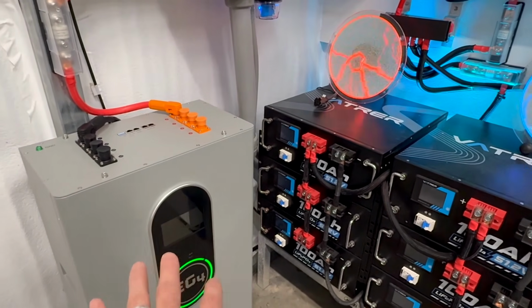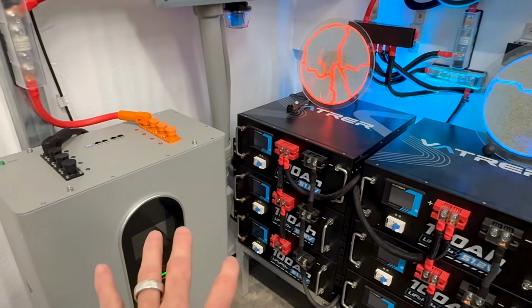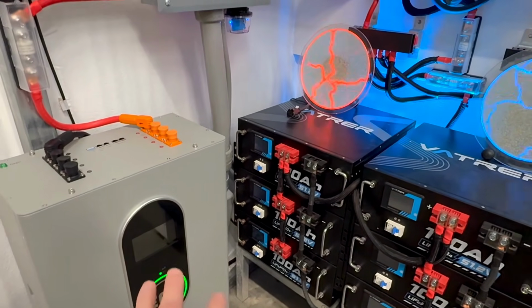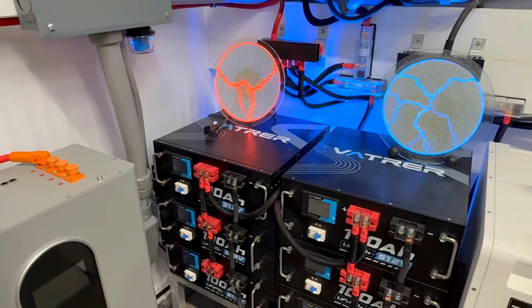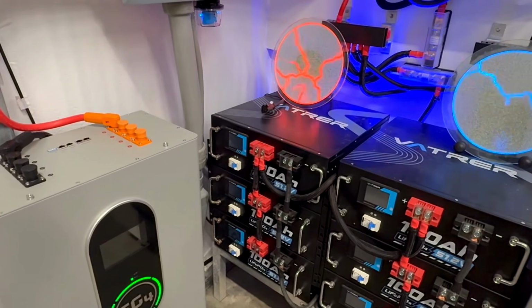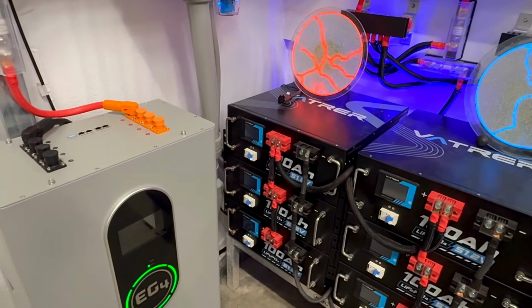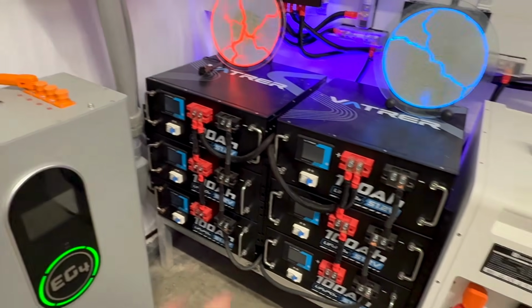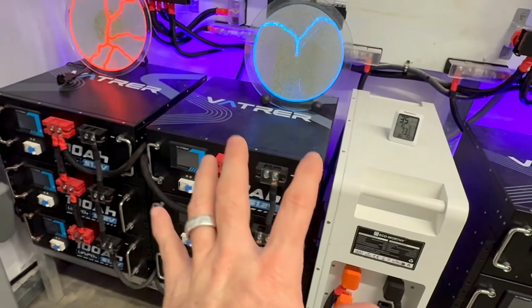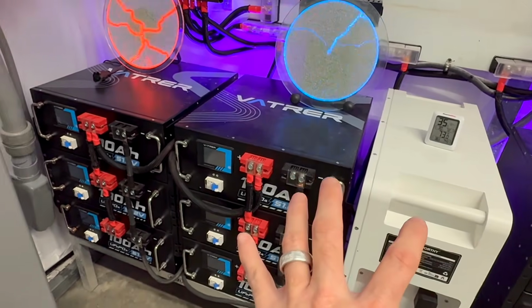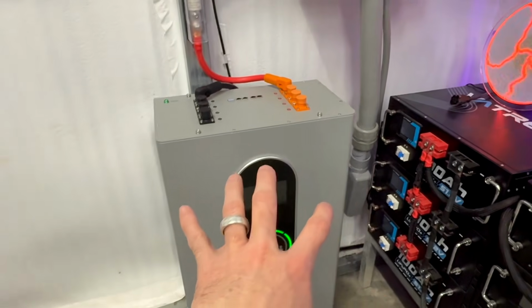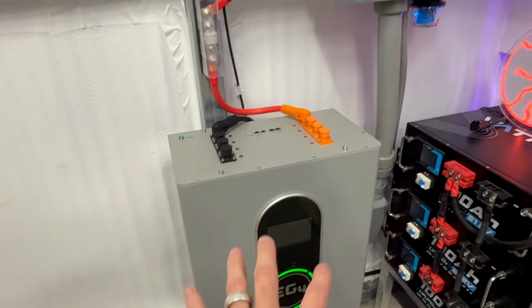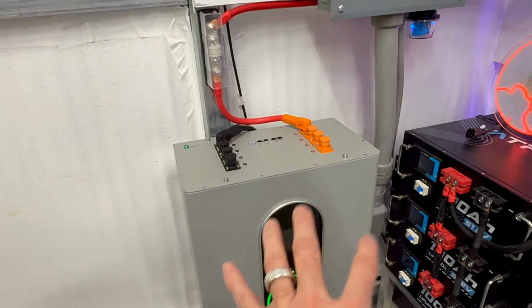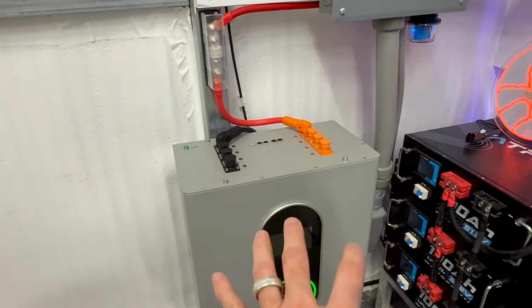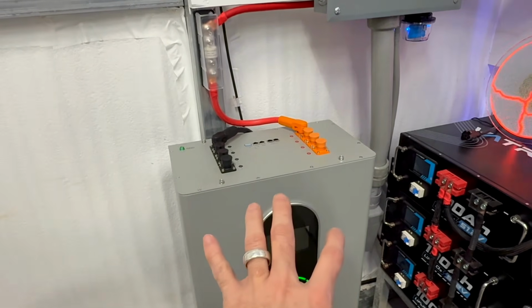Circuit breakers on all the batteries is something you should look for, but fuses are a great way to add additional redundancy. Another thing to note: whenever you're connecting up your batteries, say you have an existing bank, charge your bank up to 100% and then charge your new battery up to 100%. Then, when they're both at 100%, only then do you add that new battery in.